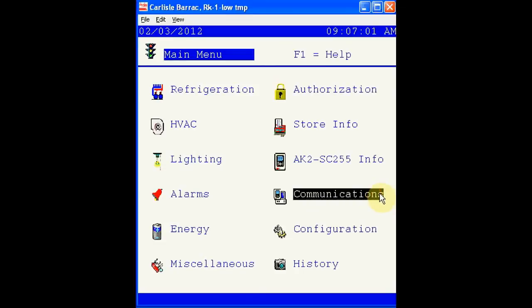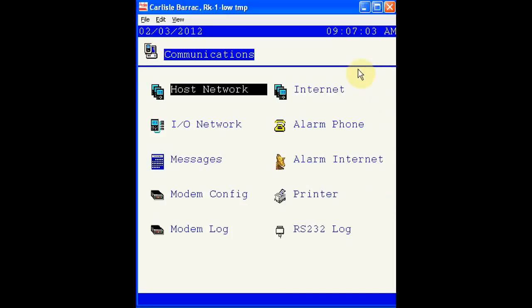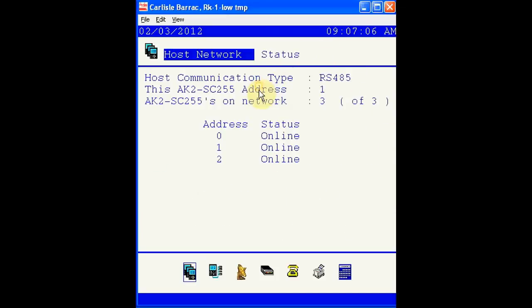Let's start with communications. As we said, host network is a list of other controllers connected on the 255 network. These can be connected through a 2-wire RS-485 network or Ethernet. As you can see, there are a total of 3 units on this network, and all 3 are currently online. Unit 0, Unit 1, and Unit 2. Unit 0 is defined as the master controller.